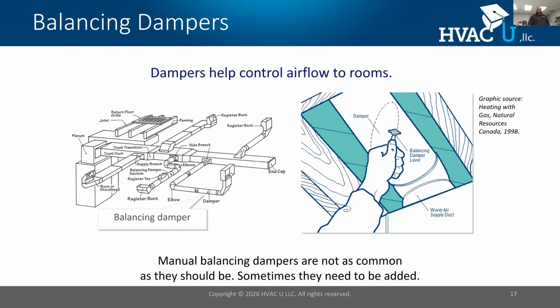Let's talk about balancing dampers. Unfortunately, when it comes to ductwork, this is often what I see that's never done. What is balancing? Balancing is the process where, after I designed my system with a load calc and came up with specific BTUs and CFM for rooms, I design a duct system to deliver the CFM to those rooms. When I design my CFM to go to those rooms, I need to commission it. So I need to take a device, maybe a flow hood, and verify that I have the CFM coming out of the ductwork that I designed for. We call that commissioning or balancing.